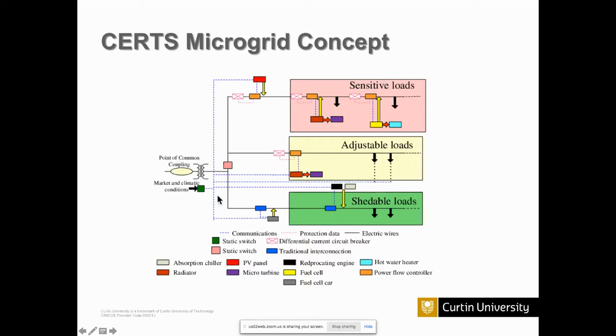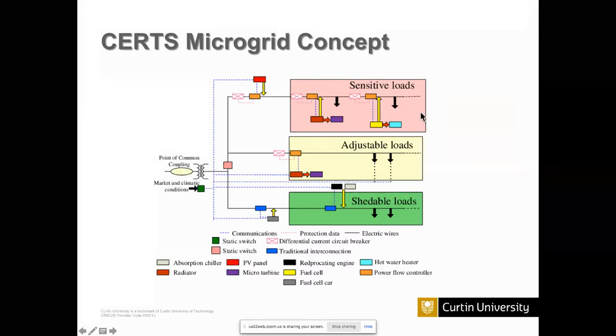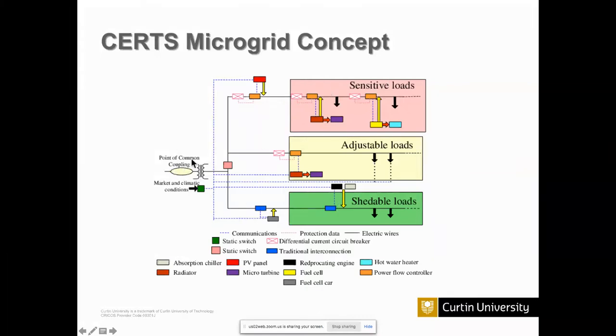And this microgrid is connected to the utility at the point of common coupling, we call it PCC. Usually the utility will be connected to the microgrid at one point of common coupling. The basic reason is that suppose there is another connection here, or even here, and when you want to island, you have to disconnect both switches. Because if you disconnect it here and it's still connected here, the whole thing is still connected to the utility. So according to this, you have a disconnection at this point.